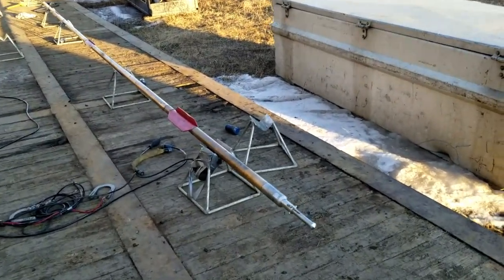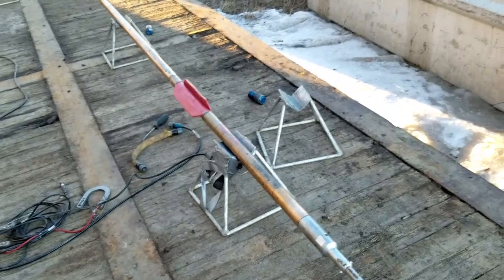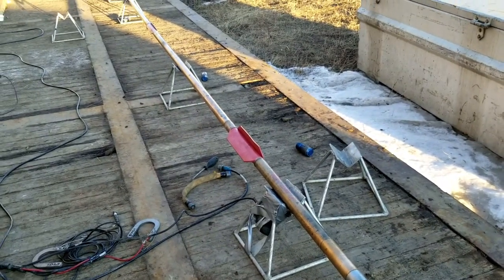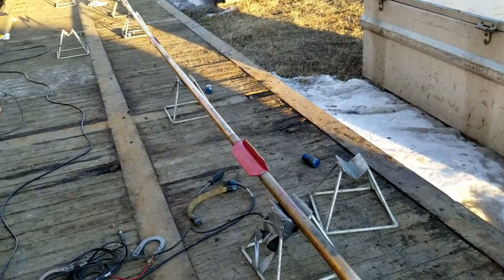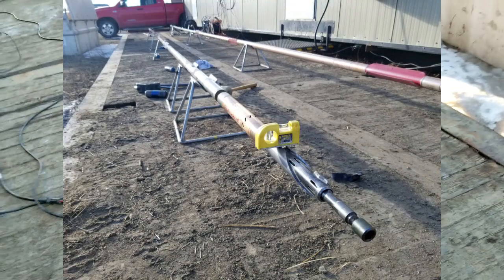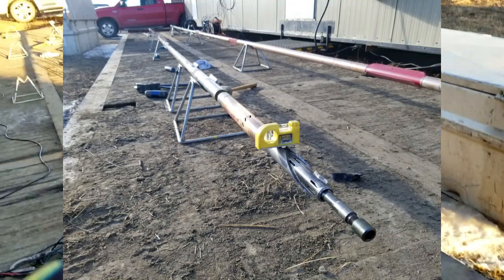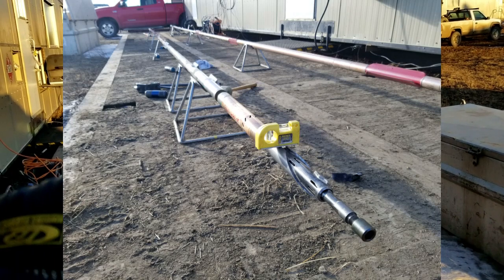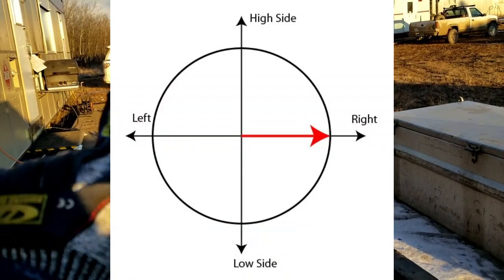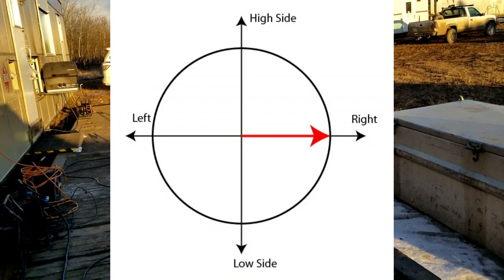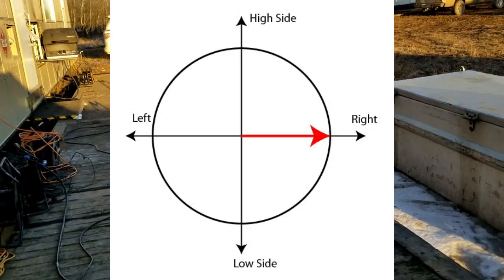Another piece of equipment we use here is for testing after programming and configuring, and reading tool configuration from the tool's memory. We have to do the roll test, where with that level we do high side, and 90, 180, and 270 degree roll tests.